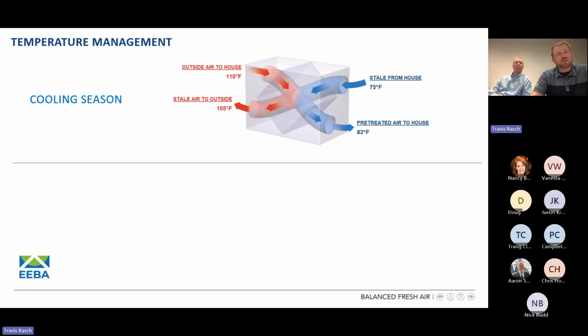If we look at a cooling season, so let's pretend we're in Phoenix, Arizona. It's 110 degrees outside. I've cooled my house down to 75 degrees. What we're going to do is take that difference between the outdoor air and the indoor air, and we're going to recover a certain percentage of that. So as you can see in this example, we're using that 75-degree stale air from our house to cool down that incoming outdoor air at 110. By simply moving this air through that recovery core that we talked about earlier, we're able to take that 110-degree air and temper it down to 83 degrees in this example. And again, that's just the percentage of the delta, or the difference between that outdoor air and that indoor air, to determine what we're going to deliver to the home after it passes through this product.